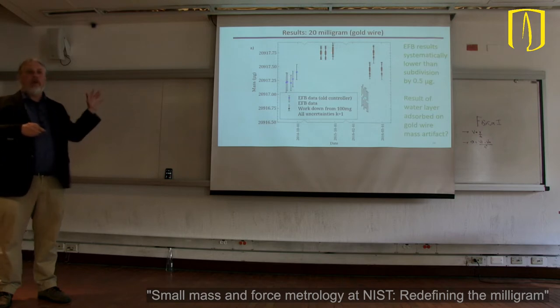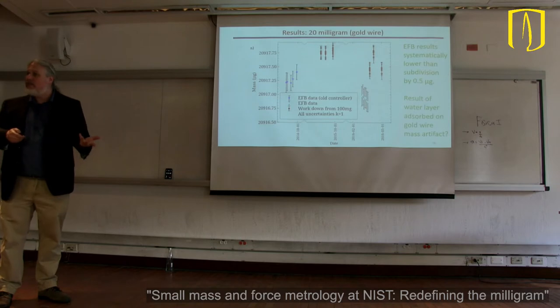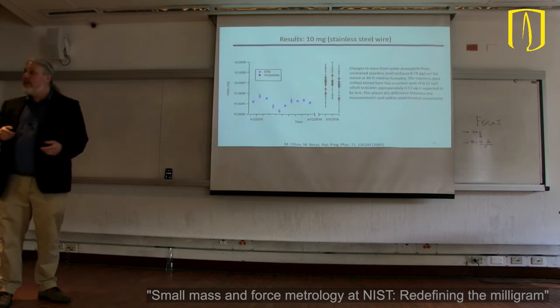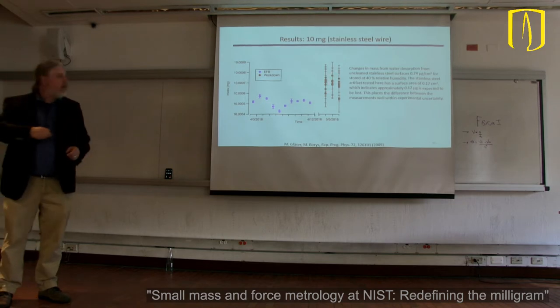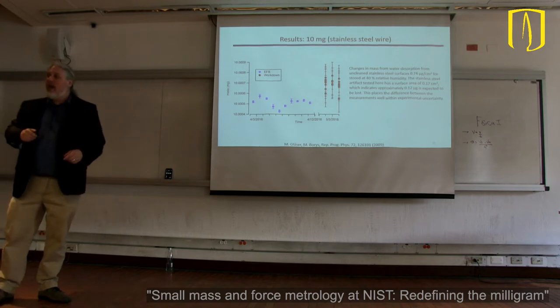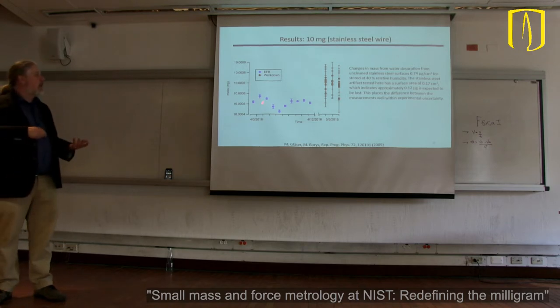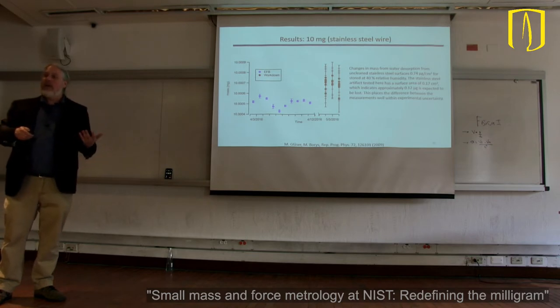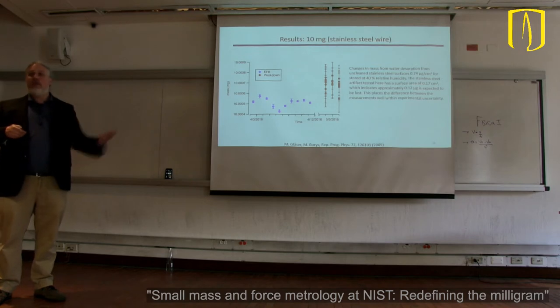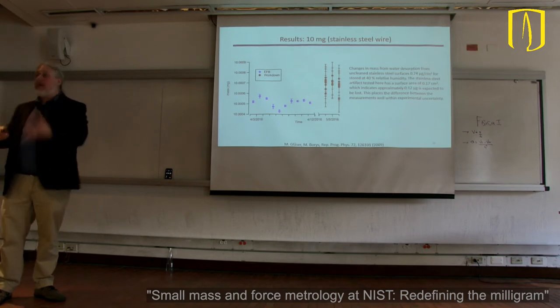Nobody uses gold masses, but what's much more common is a stainless steel mass. And you see the effect here too. So this is our electrostatic force balance. This is our subdivision method. And we're just a little bit lower here. Looking at the literature in terms of what you expect to see from water desorption, we're at about the right range. So we think we have a good handle on what we need in order to do mass measurements out in the world, to use the electrostatic force balance as our primary standard for mass.